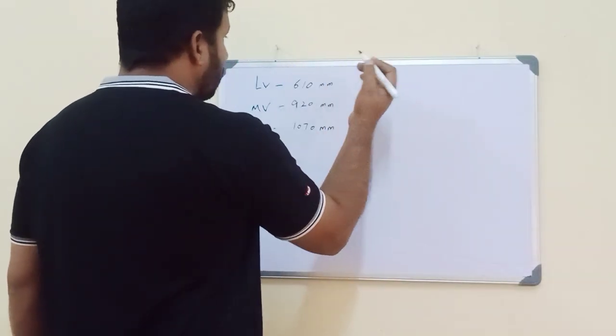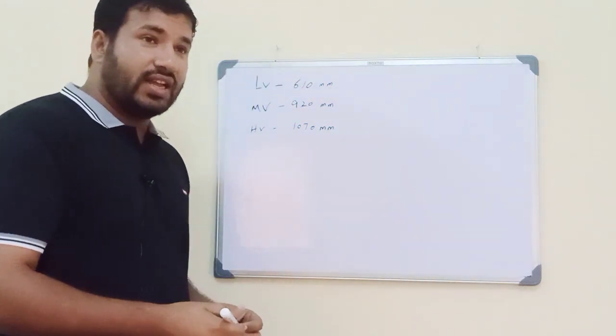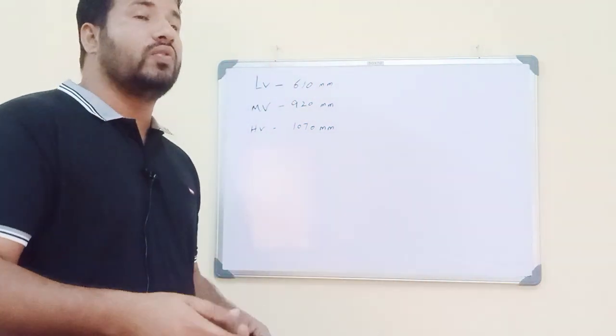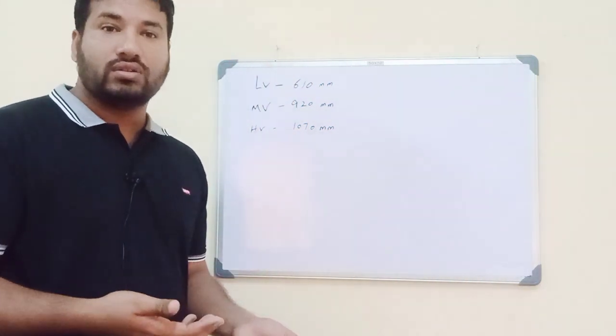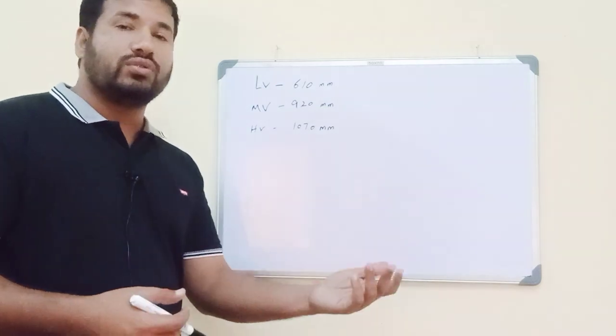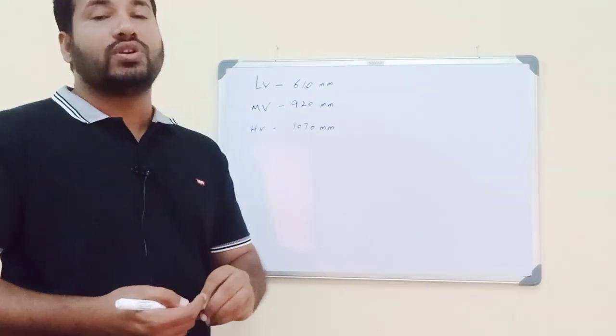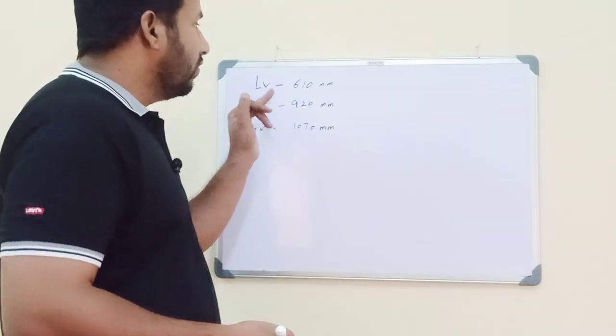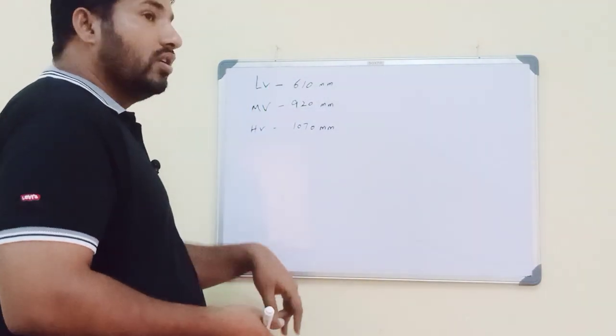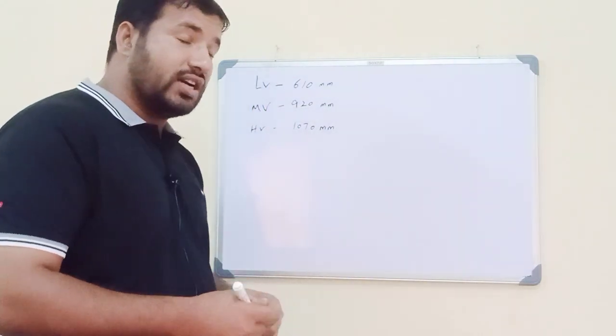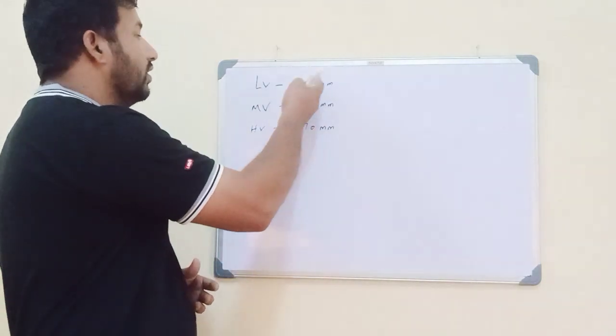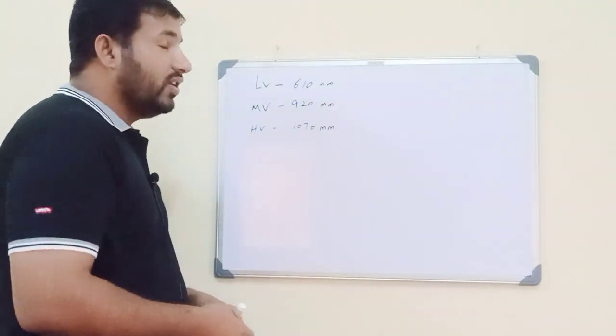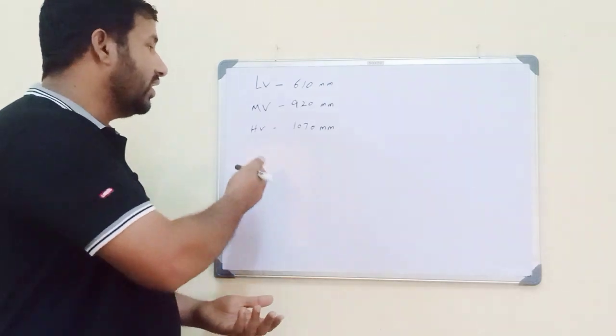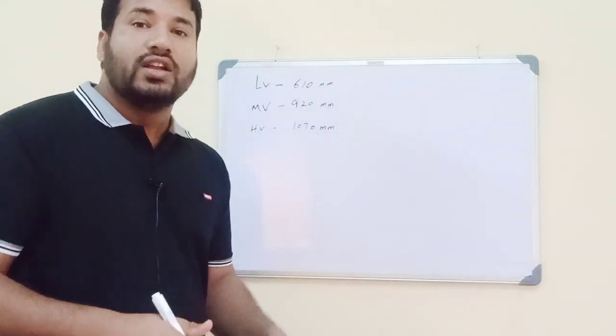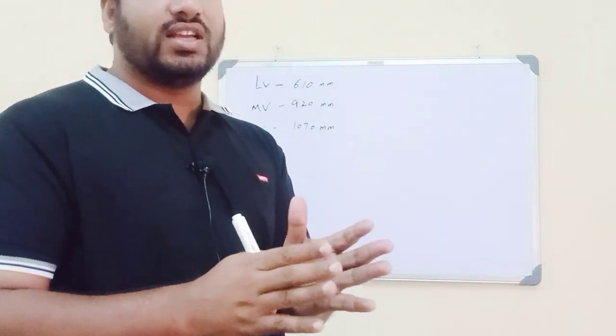This is direct buried. Same thing, when we go to conduit there is a difference, and if we go to duct bank, it's also different. Like if we go to duct bank, it's 460 for all. If we go to conduits, PVC conduit or PVC coated RGS conduit, then LV is 460, MV is 710, and HV is also different.